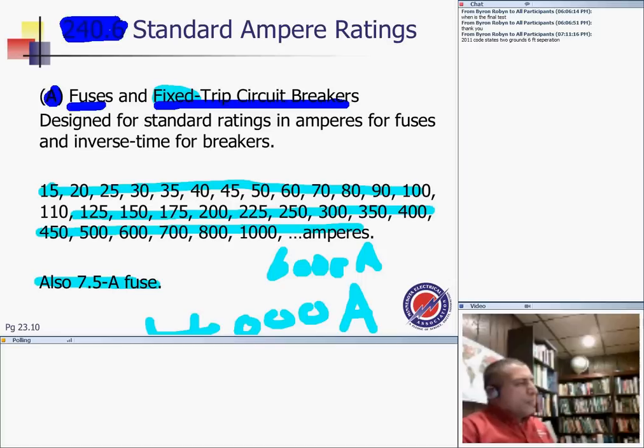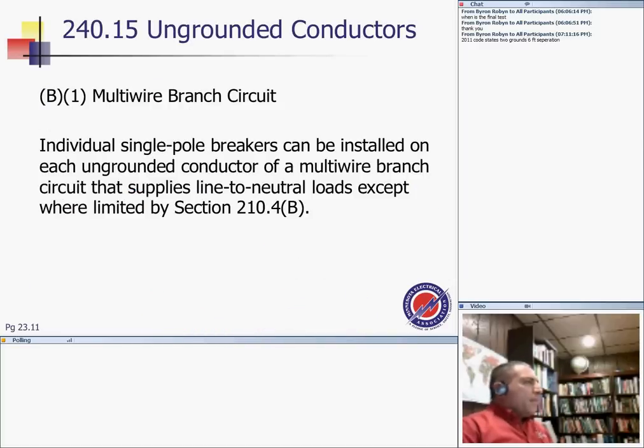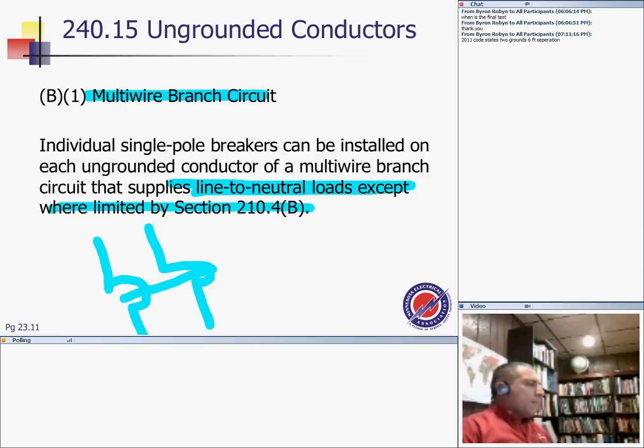For fuses, there's also a couple of other things. If you have ungrounded conductor, guys, with multi-wire branch circuit, as we all know, multi-wire branch circuit shall be only installed on ungrounded conductor. Multi-wire branch circuit will supply line to neutral loads, except where limitation. There's some limitation where, if you have here's a multi-wire branch circuit here. For the most part, it has to feed line to neutral load. Here's line to neutral load, and here's my neutral, shared between.